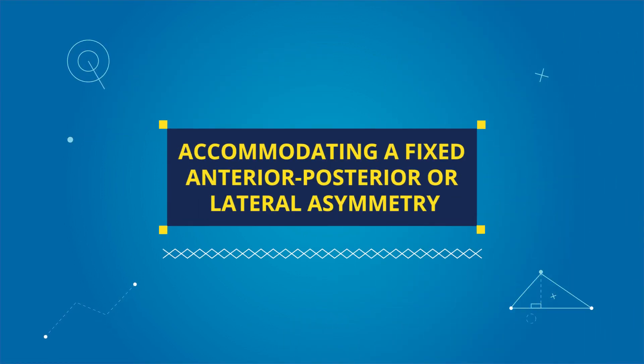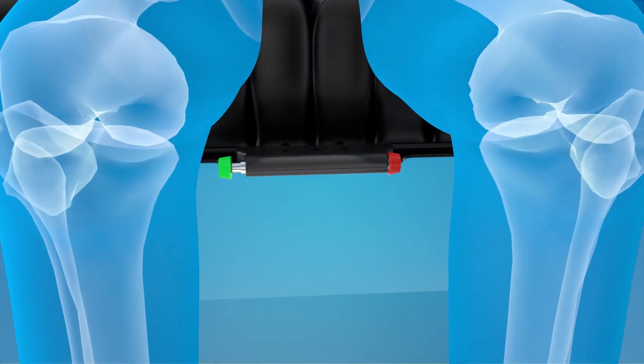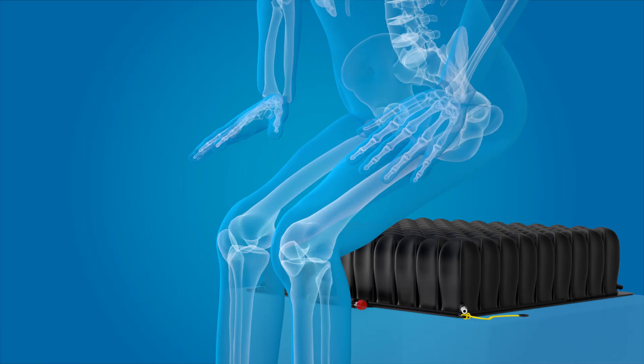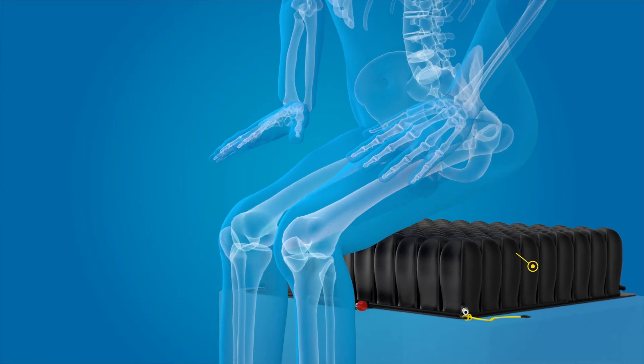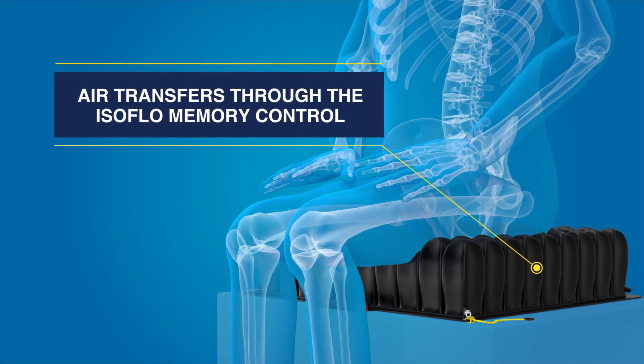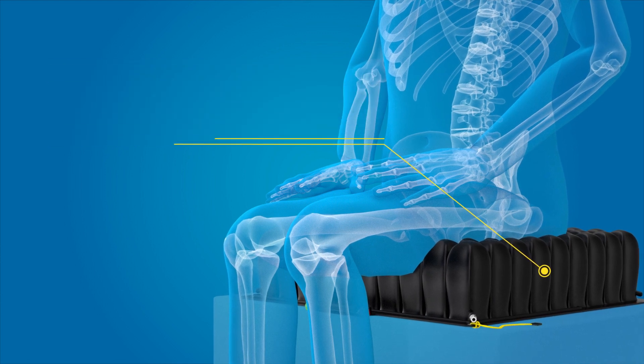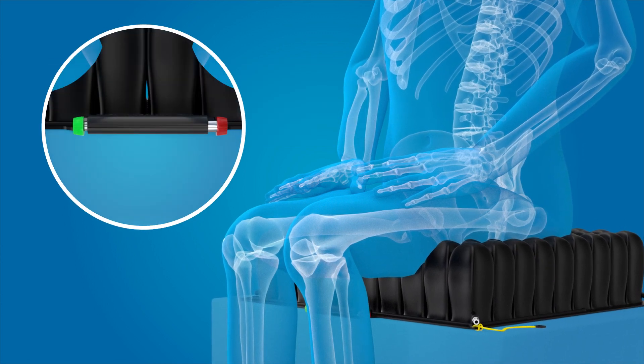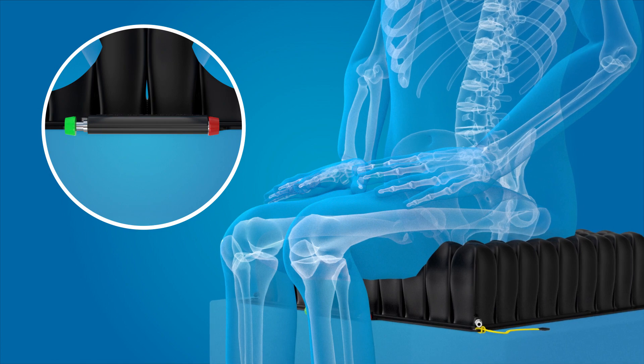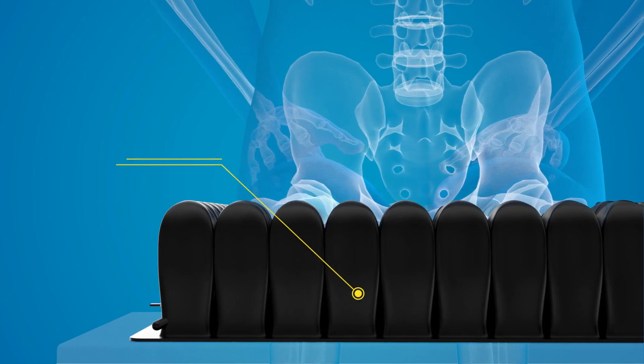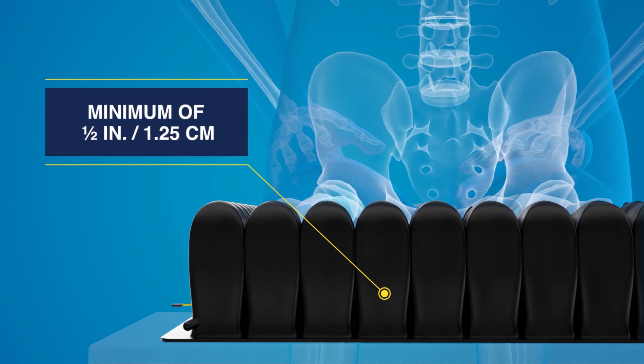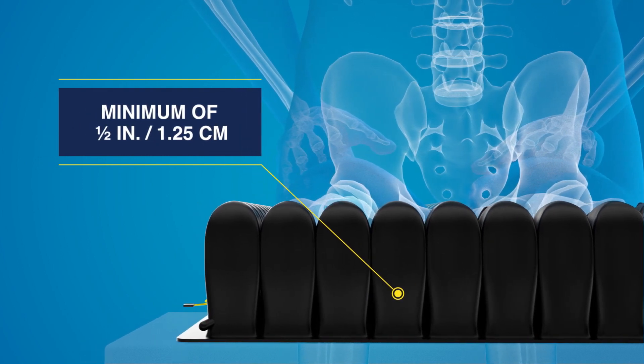To accommodate a fixed anterior-posterior or lateral asymmetry, make sure the isoflow control is open by pressing the green knob in. Have the client sit in their normal position while the air transfers through the isoflow memory control. When the air transfer is complete, close the isoflow control by pressing the red knob in. Perform a hand check to ensure there is a minimum of one-half inch of air between the client's ischial tuberosities and the seat surface.